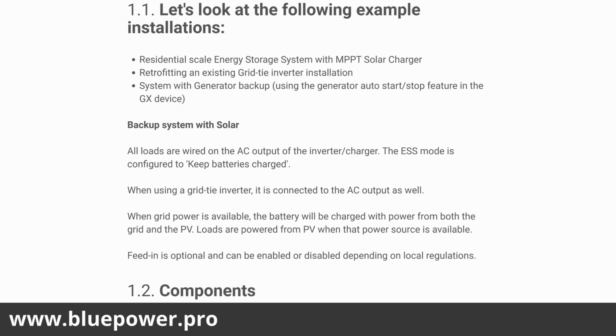So let's have a look at some example installations over here. Here's a backup system with solar. All loads are wired on the AC output of the inverter. ESS mode is configured to keep batteries charged. When using a grid-tied inverter, it is also connected to the AC output. When grid power is available, the battery will be charged with power from both the grid and the PV. Loads are powered from the PV when that power source is available. Feed-in is optional and can be enabled or disabled depending on local regulations.